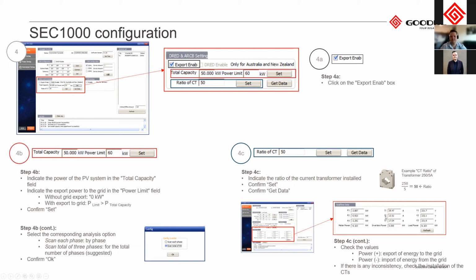Then next to the P1, P2, P3, we have the currents, and that's the currents which our CT is reading, and the voltage reference, which we can see. So if we take this current and the voltage and we multiply them, then we should get a value close to this number. If our value is widely out, it may be that our voltage reading is not coinciding with the current reading, so that we aren't getting a correct reading here. But we also just have to take into account the power factor. So the site's power factor may not be ideal. That's why if this is very close to one another, equipment shouldn't be affecting this too much. Normally we'll have a 0.9, 0.95, something like that. That's why you'll only see 95% of your calculation here as actual power. But if you're seeing less than 50%, it could indicate an issue with your voltage reading versus your current.